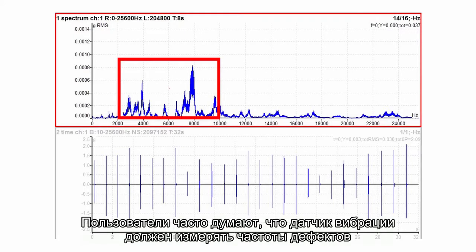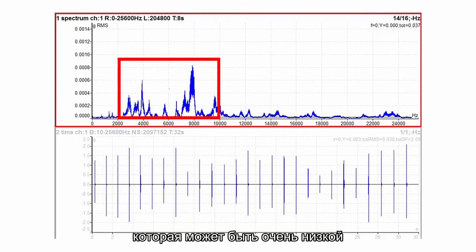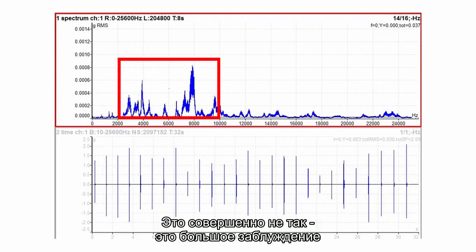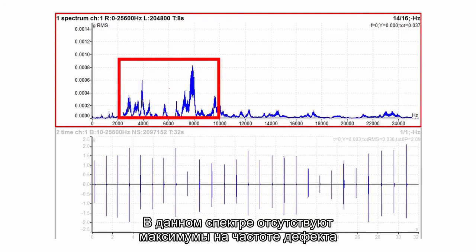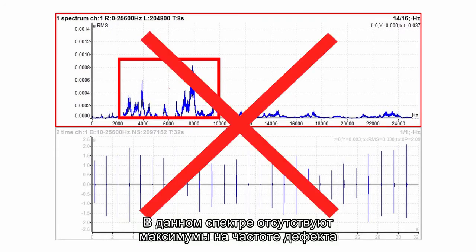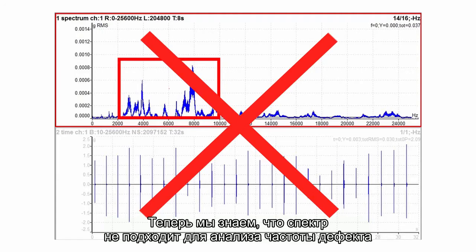Users often think that the accelerometer must measure the fault frequency which can be very low. Absolutely not. It is a big mistake. This spectrum doesn't contain the fault frequency peaks. Now we know that spectrum is not a good tool for fault frequency analysis because they are not visible in normal spectrum.